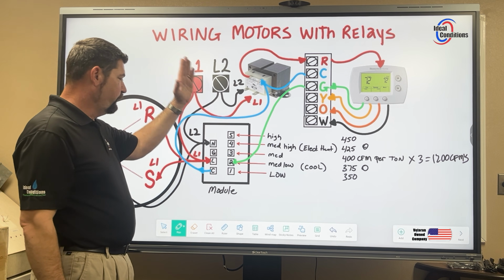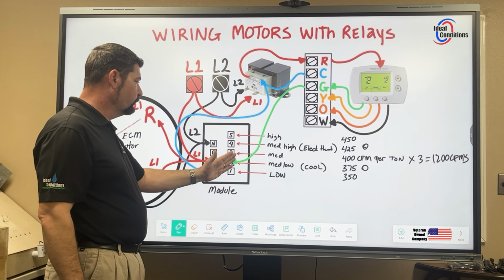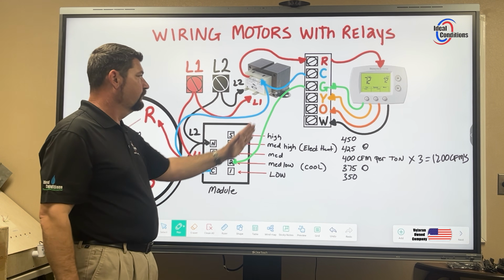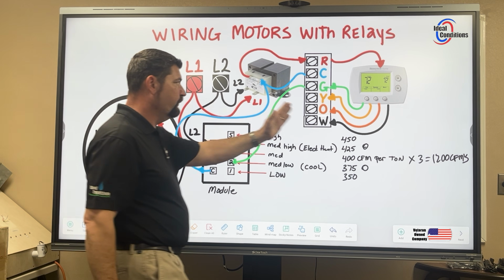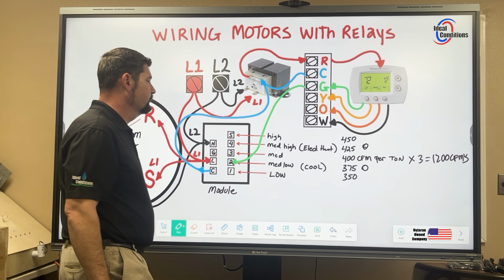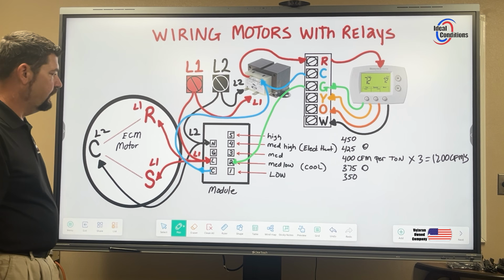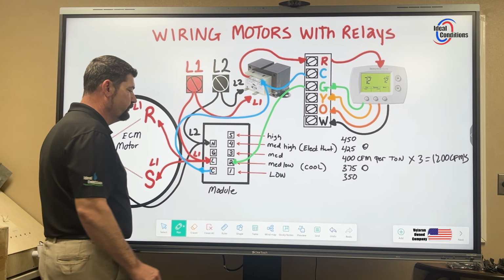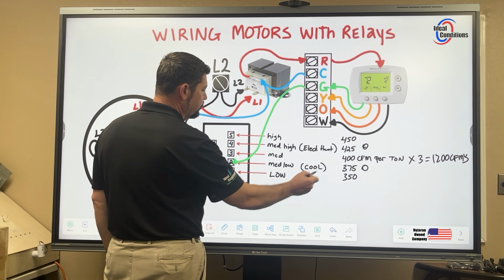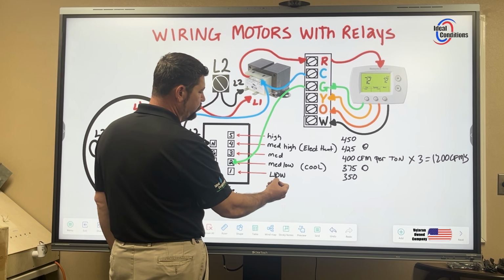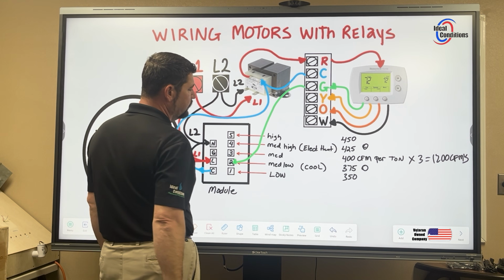So 1 through 5 are all low voltage 24 volt inputs. Path is from the thermostat, okay? And they typically wire to terminal 2, which is medium low, which in between each one of these is 25 CFMs difference.